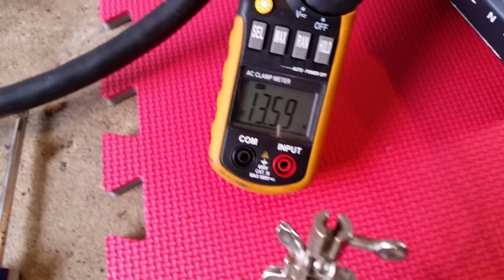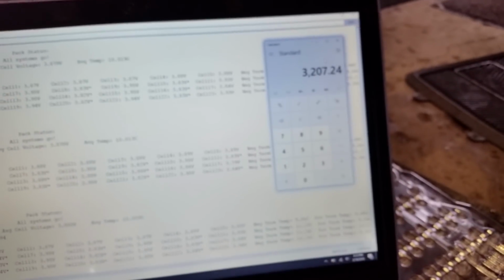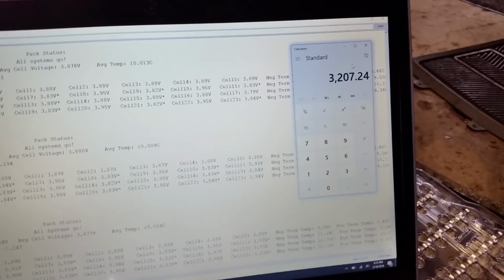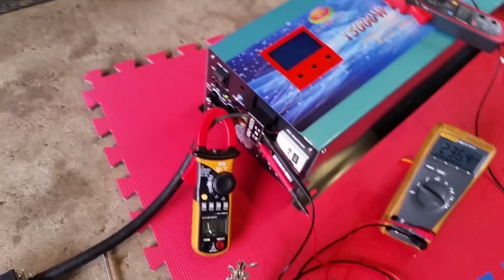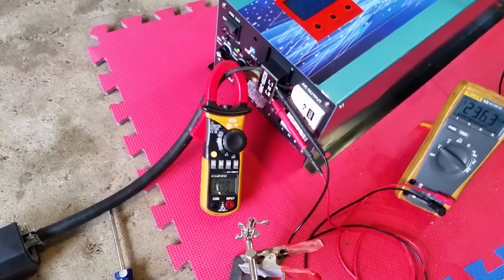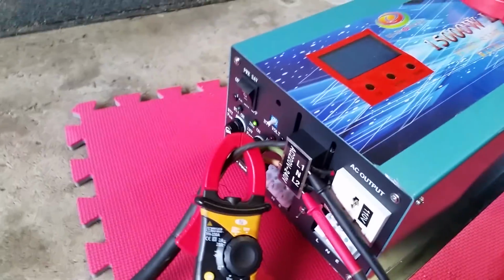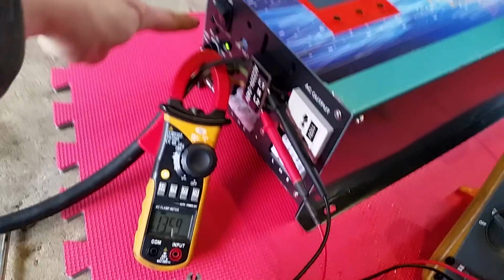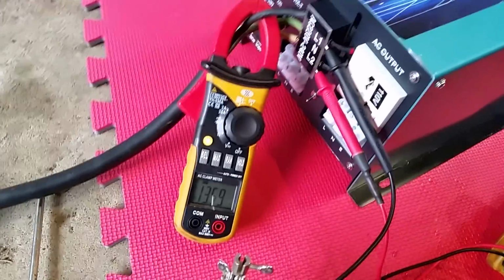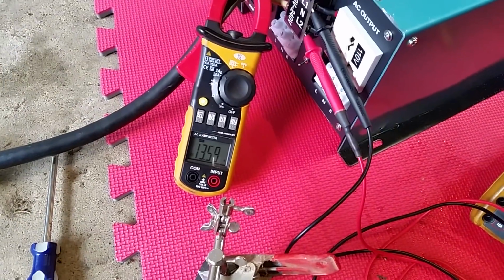And this one here is still 13.59, and 236. 236, 3.2 kilowatts. All right, I'll do the math later for the efficiency. But so far this is as expected because I'm being gentle. This is a 20 amp circuit breaker or fuse in here, so I'm not going to exceed that right away. I'm going to get up there gently.